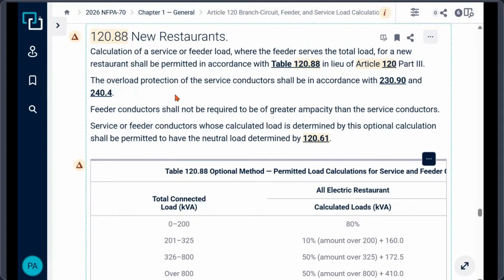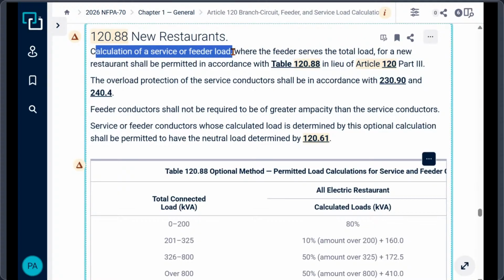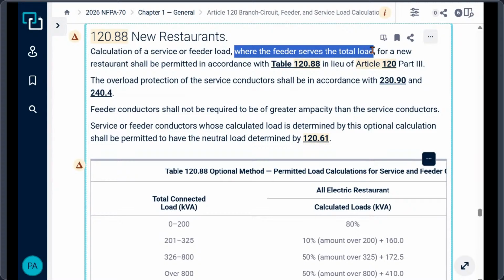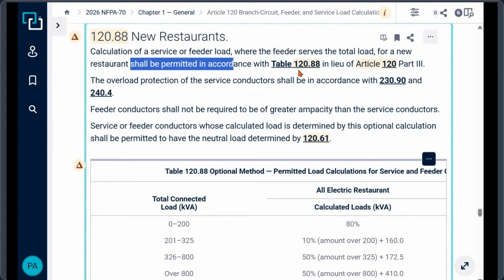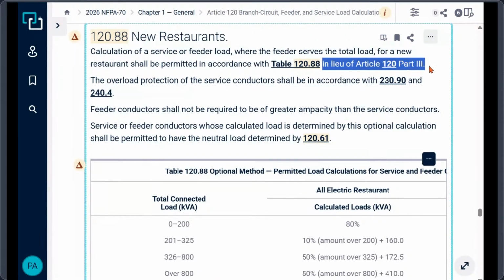All right, so it says calculations of a service and feeder loads, where the feeder serves the total load for a new restaurant, shall be permitted in accordance with Table 120.88, right here, in lieu of Article 120 Part 3, which is the same as Article 220 Part 3.